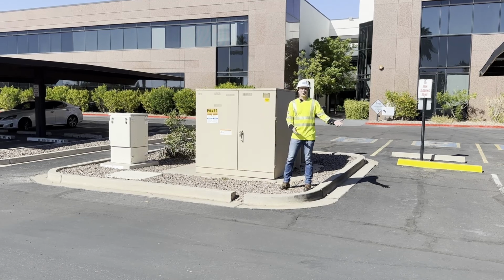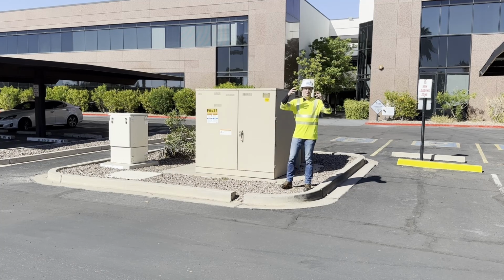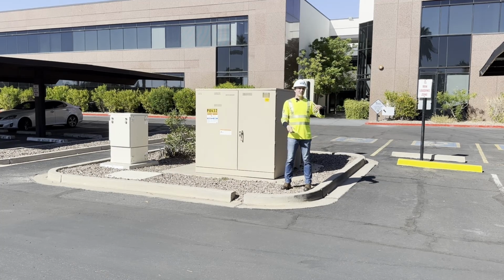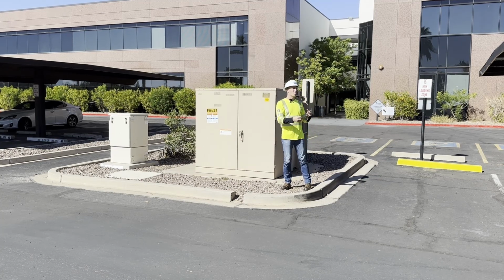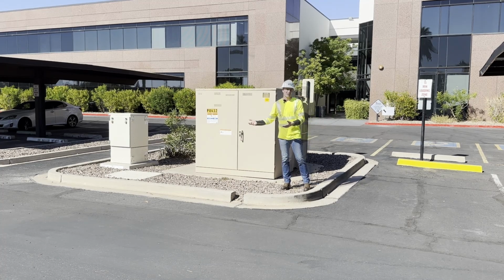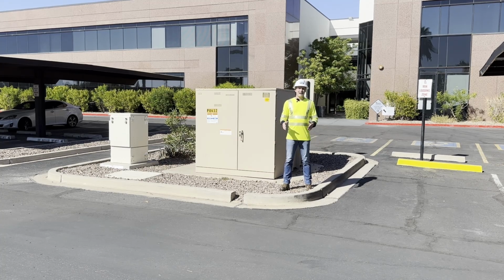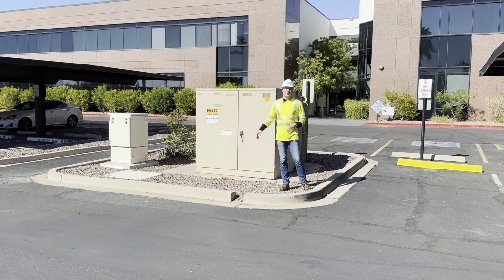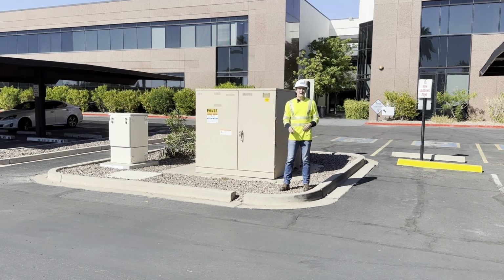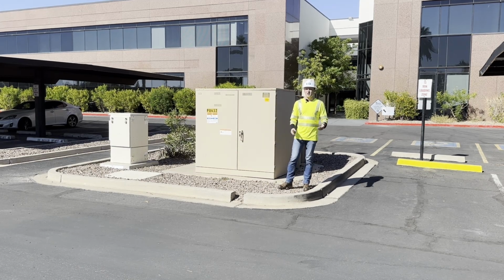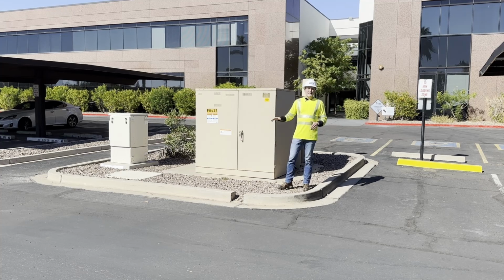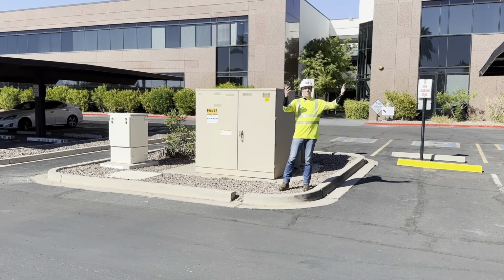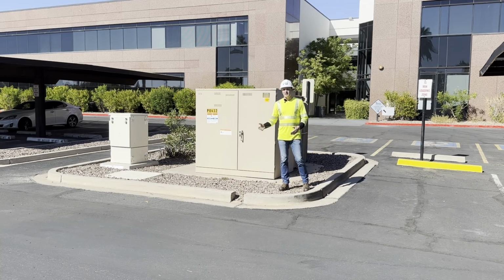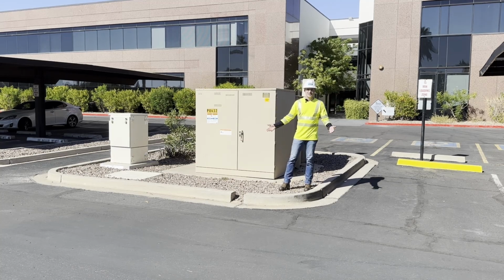electric vehicle charging infrastructure projects. The small little overhead transformers that we'll see, that's the second kind, for residential homes or small commercial buildings, can't satisfy the load that we need for DC fast charging. In general, anytime you go above roughly 500 kVA in size, you're going to need a pad mounted transformer. Sometimes though, you can creep up to 750 kVA depending on the utilities' ESRs, but for the most part, anything under 500 kVA is going to be an overhead transformer. Anything above that is going to be a pad mounted transformer, as we see here.